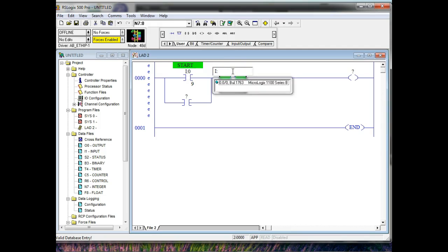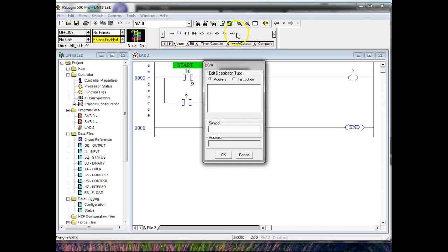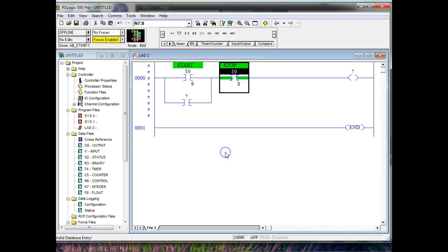So N7:0/8. And then we'll call this gator stop. Now in motor controls, and don't ask me why, we usually put the stop on the L1 side. On PLCs, they usually put the stop after the seal-in. This is just the way they like to program. This is definitely the way they do it in Germany. Output, colon, don't ask me why.